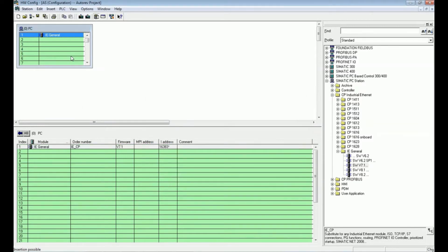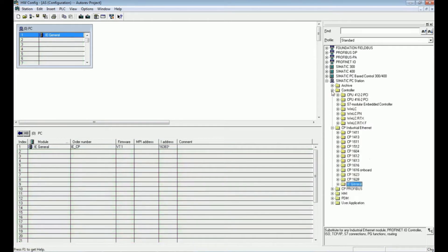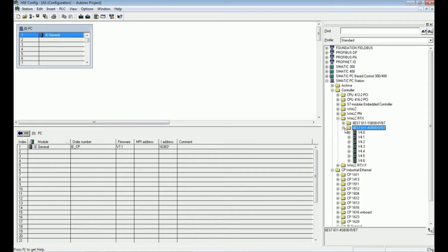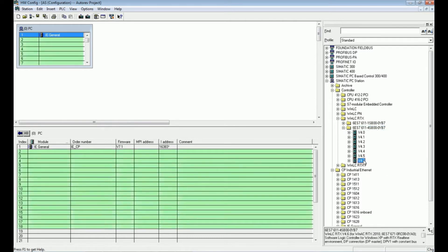After successfully adding IE General, we will add the CPU. Go to the Controller option and select 'Win LC RTX Box'. In Siemens, different DCS or automation stations are available — the RTX Box is working as our automation station here, though in field areas an S7-400 system is also sometimes used as a DCS. We have version 4.6 of the RTX Box, and I will drag and drop it into the rack.